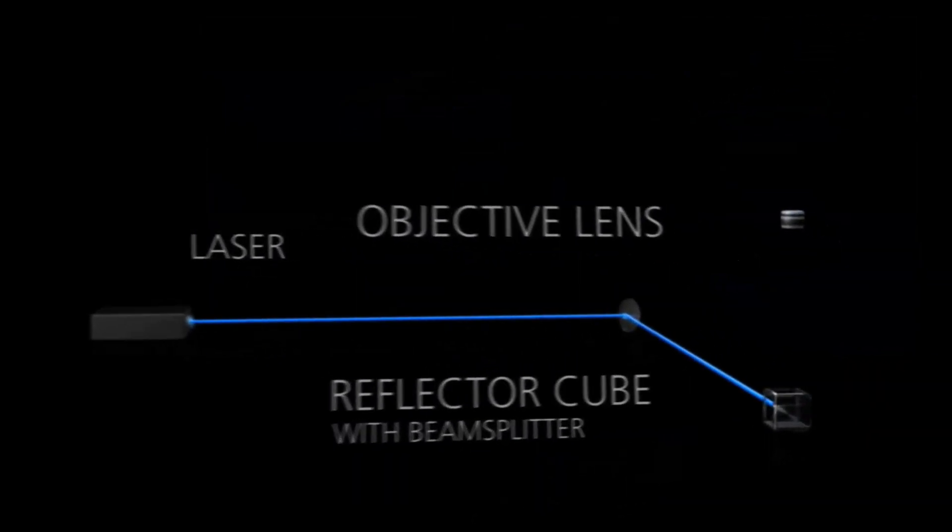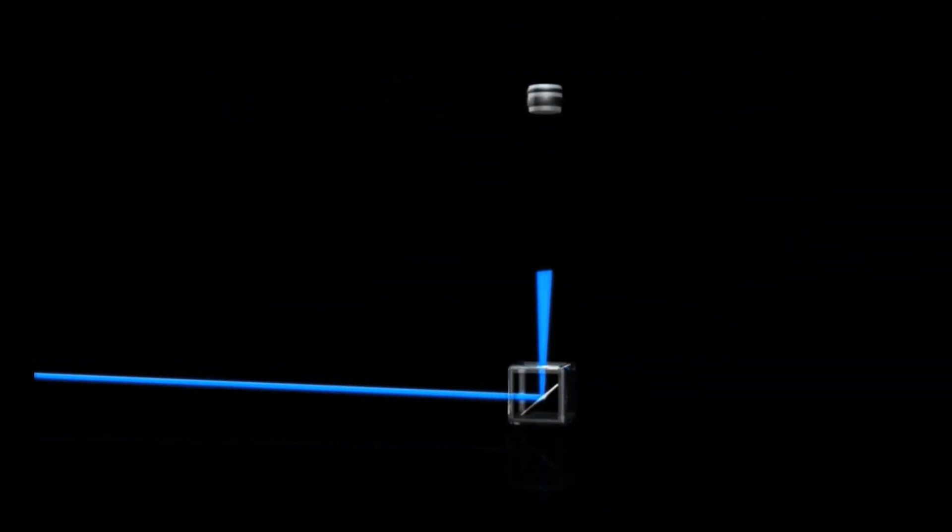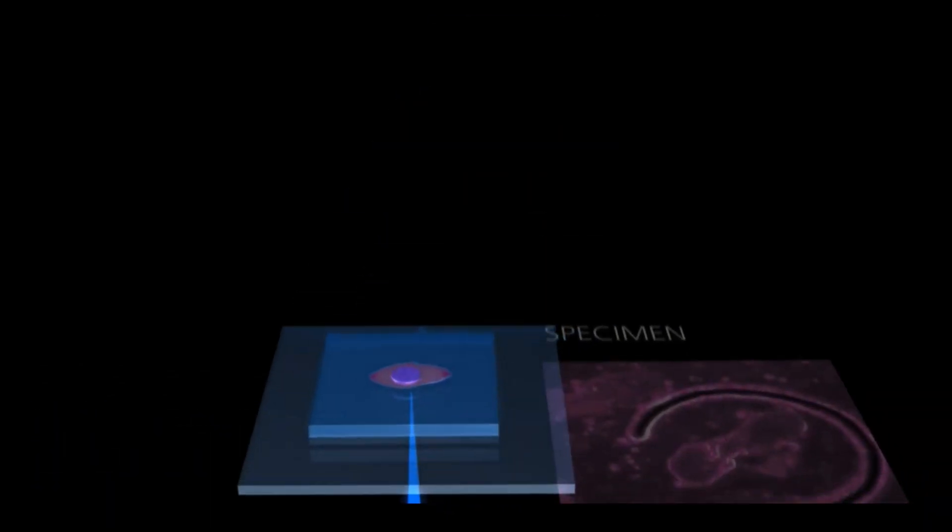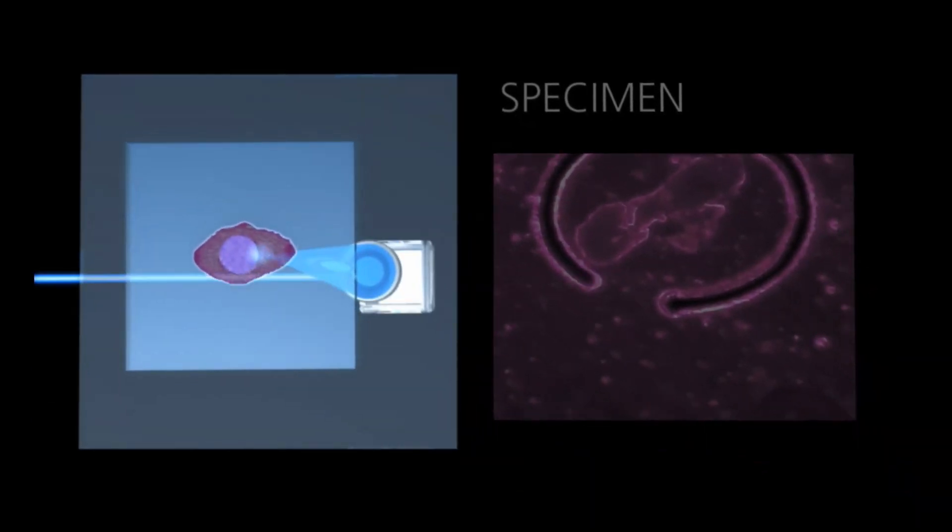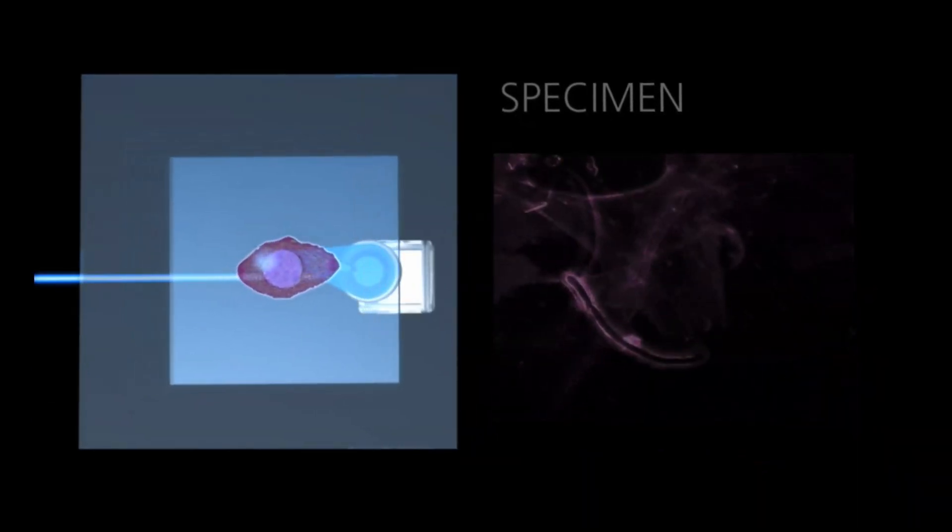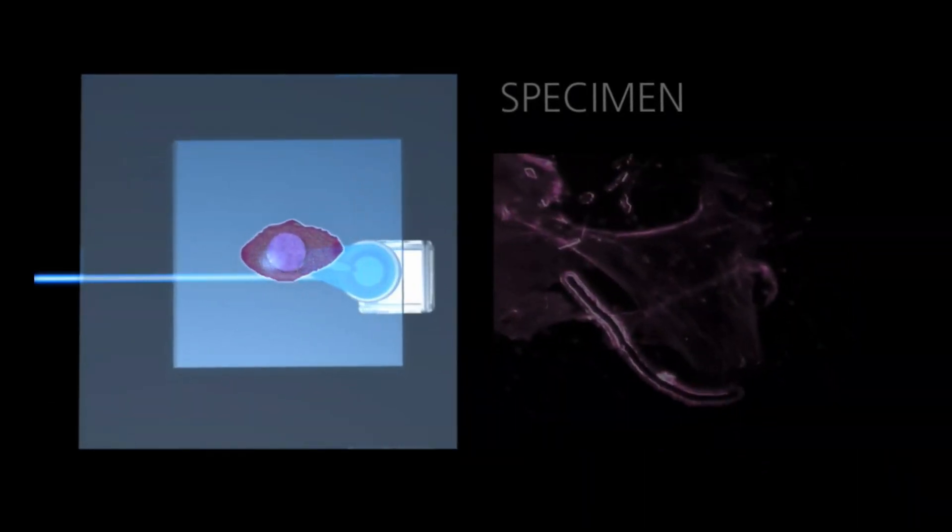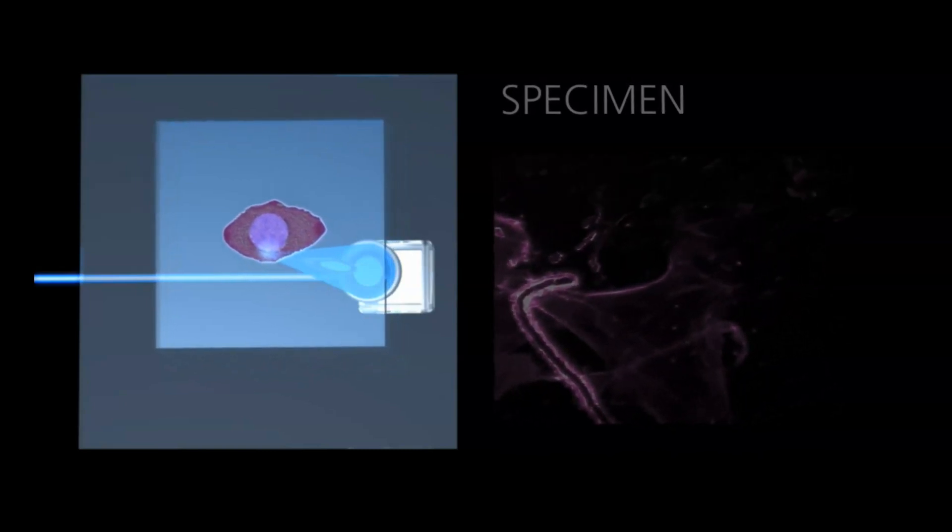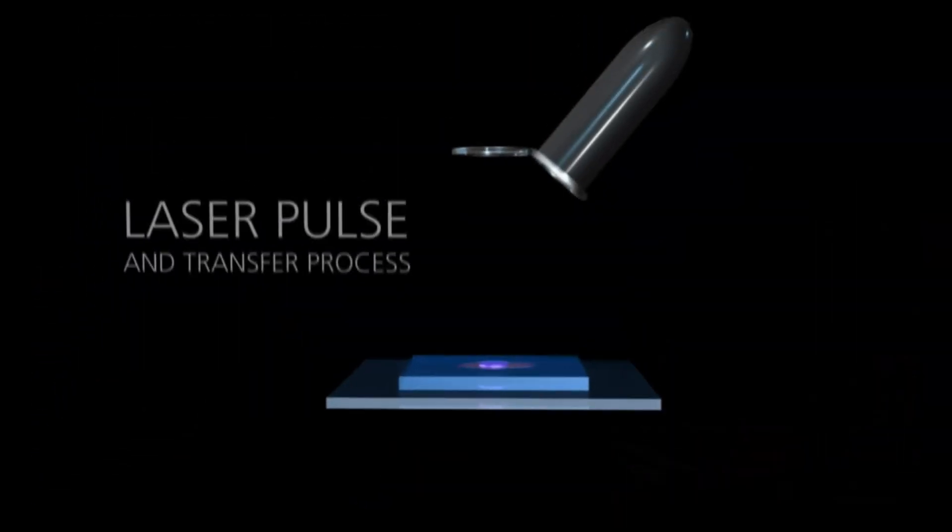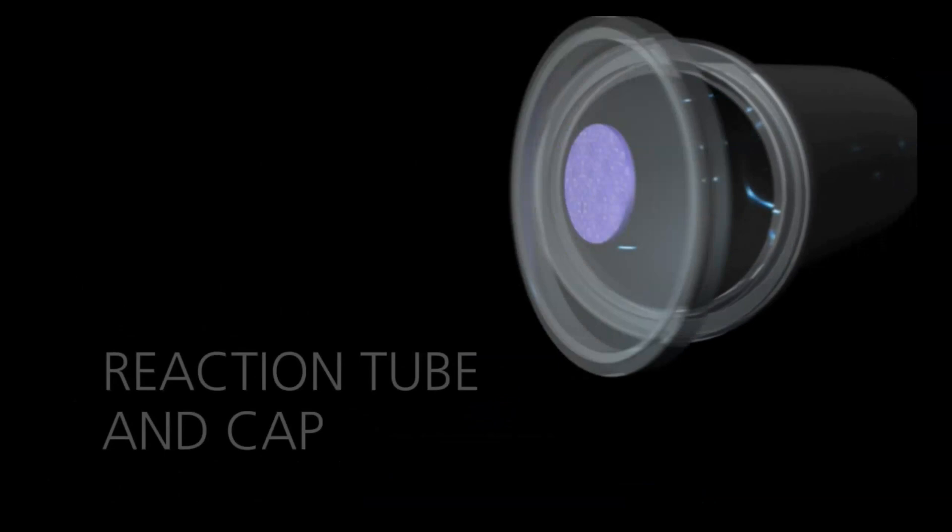By focusing this laser on the sample and moving the stage, it is possible to locally ablate tissue in a manner that permits isolation of regions of interest. A defocused pulse of laser is then applied, causing the generation of highly localized plasma at the interface between tissue and slide, propelling the tissue off the slide and into the collection tube.